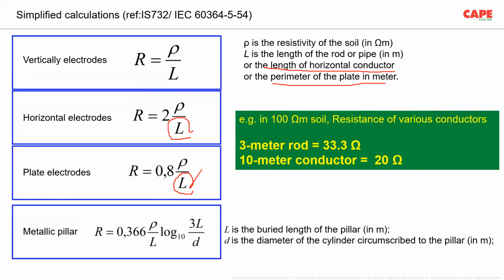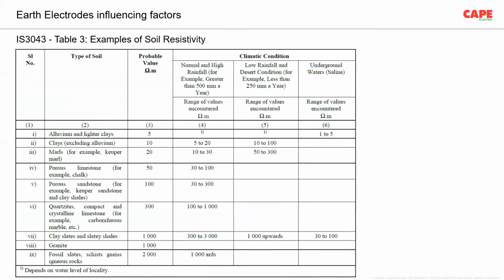Imagine you have a 100 ohm meter soil and you have a 3 meter rod, then the earth electrode resistance is 100 divided by 3, approximately 33.3 ohm. If you have 100 ohm meter soil resistivity and a 10 meter conductor horizontally, then the resistance is 20 ohm. So by making these simple calculations, you can find out the resistance of the earth electrode in soil. Technically speaking, for low voltage application, you don't need to make such an accurate calculation because it is not going to help you. Even if the earth resistance is 3 ohm or 30 ohm, it doesn't matter. So these are included in the upcoming IS 732.